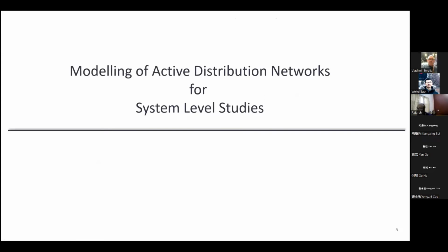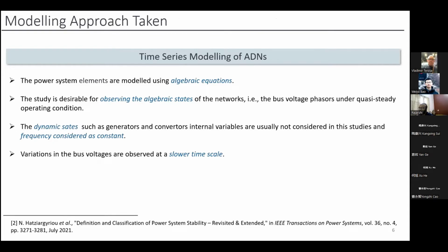Now, to perform such system-level studies in the distribution network, we first need to formulate how we model the system. So let's look at the modeling approach we are taking. For this kind of study, we are taking the time series modeling approach of active distribution networks. We are only interested in finding the algebraic states of the system, which are typically the bus voltage phasors, and therefore most of the equations involved in such modeling are algebraic equations. This kind of study is applicable for observing the algebraic states mostly. The dynamic states, such as those of generators or converters, if there are any converter-interfaced renewable sources, have internal variables that are not observable using this modeling scheme.